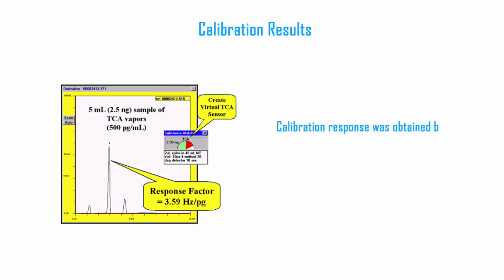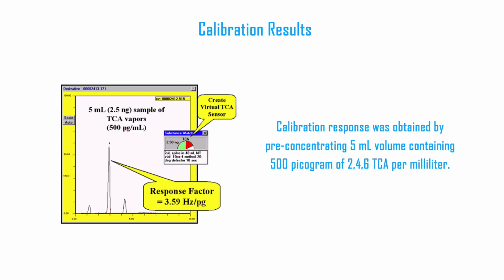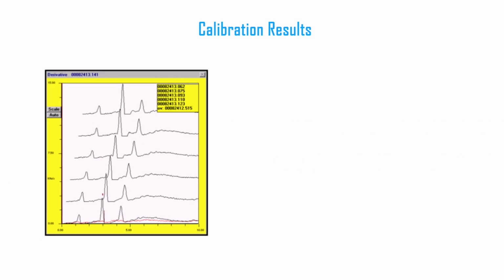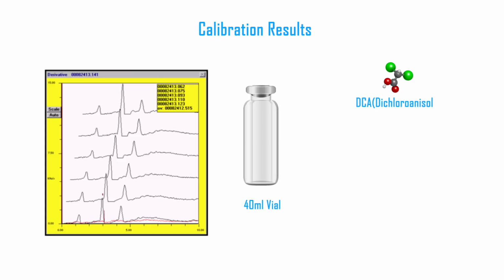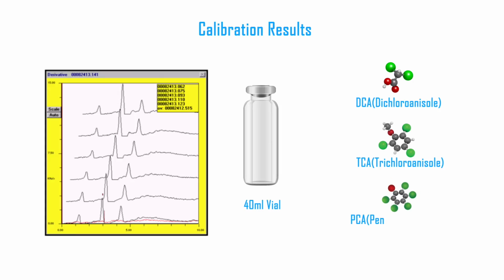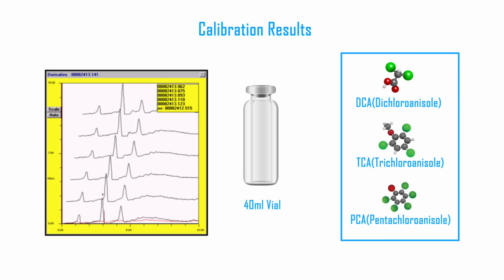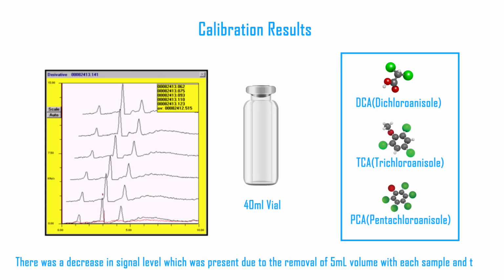Calibration results: the calibration response was obtained by pre-concentrating a 5 ml volume containing 500 picograms of 2,4,6 TCA per milliliter. An offset waterfall display showed repeatability across 6 consecutive measurements of a 40 ml vial containing DCA (dichloroanisole), TCA (trichloroanisole), and PCA (pentachloroanisole) vapors. There was a decrease in signal level due to the removal of a 5 ml volume with each sample and test.